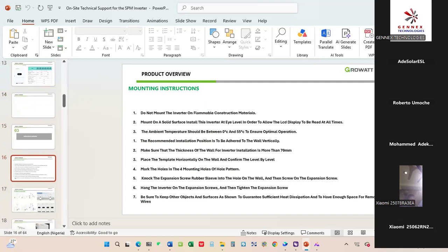Regarding the mounting instructions, like my colleagues have said, when mounting this inverter it is always advisable to give a little space between the inverters to allow air dissipation. Because when these inverters do not get air, they give an error, and the error will make the system stop working. So when mounting this system, always give a space between the inverters. The space between two inverters should be 50 cm, and the space between the inverter at the top and the one below should be 20 cm.